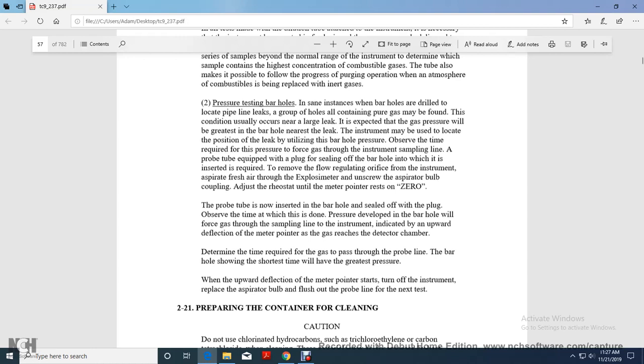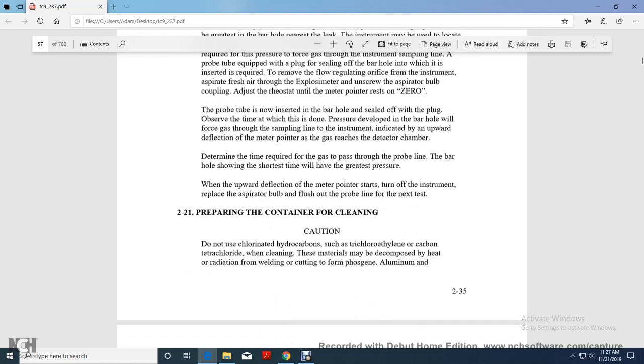Observe the time required for the pressure of the gas to move forward through the gas instrument sample line with the probe tube equipped with a plug sealing off the bar hole, which is inserted with the removal of the flow regulating orifice for the instrument. Aspirate fresh air, Explosimeter, unscrew with the aspirator bulb coupling. Adjust the rheostat until the meter points to 0. The probe tube is now inserted with the bar hole sealed off with the plug.